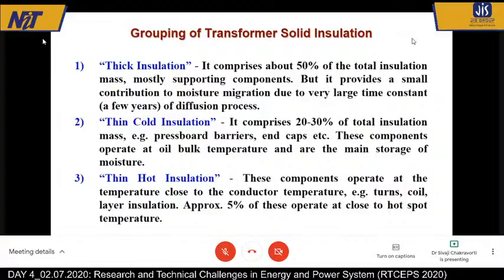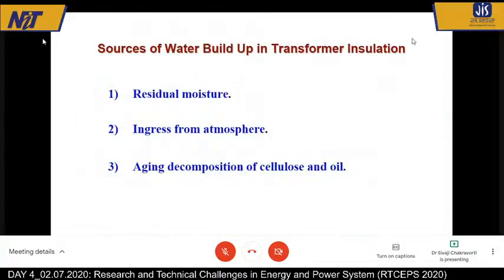They store the moisture. And then the thin hot insulation, this is generally 5% of that. And these are typically the turn insulation or the coil. So we divided the entire solid insulation into these three groups.